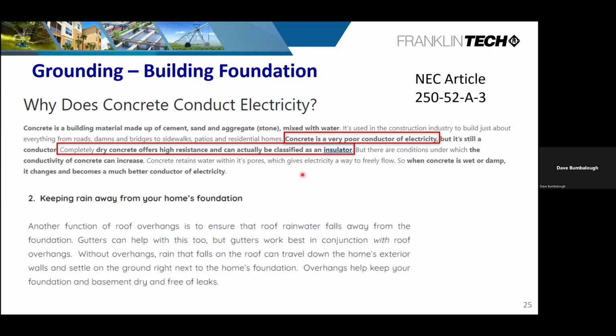To go one step further, I don't believe the electrical contractors and the building contractors talk to each other, because we put gutters and overhangs on the house to keep moisture away from the foundation, as this article shows you right here. So it's kind of a two-sided thing where both of them are negatives. And so I try to point this out when I run into these situations where there's potential shock hazard, we're having leakage, we're having issues with our controls, pump and motor failures. This is the first thing that I look for.